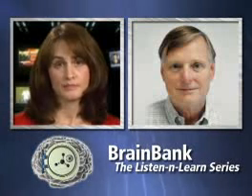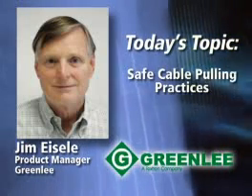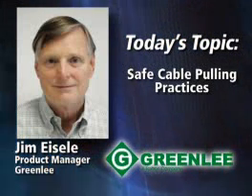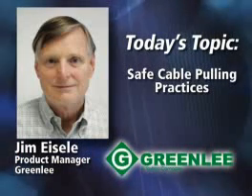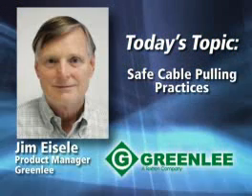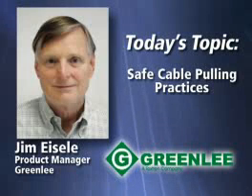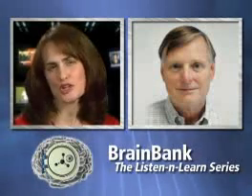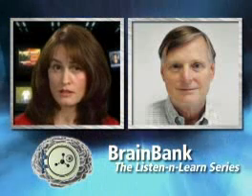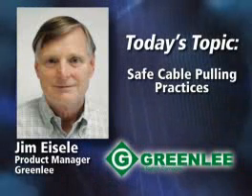Well, using the right equipment is key. The cable pulling rope needs to be rated for the maximum cable pulling force of the cable puller, and sheaves and adapters need to be set up according to the instruction manuals that come with them, so that nothing gets damaged during the cable pull, and that there are no loose pieces. So in terms of the cable, we're talking about factors that keep from damaging the cable, such as correctly sizing the bends, correct? Yes, and most of that is specified by the engineering firm that does the job.